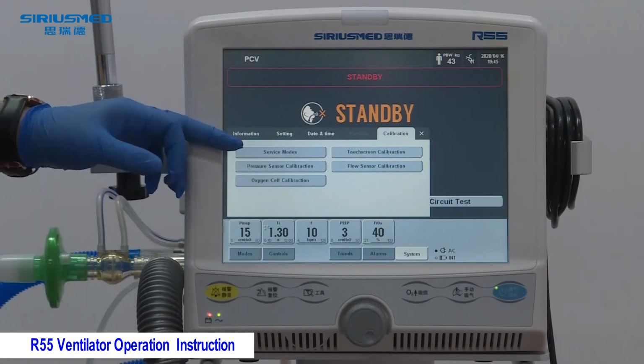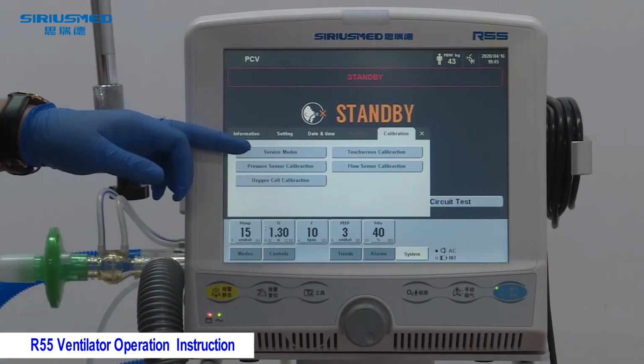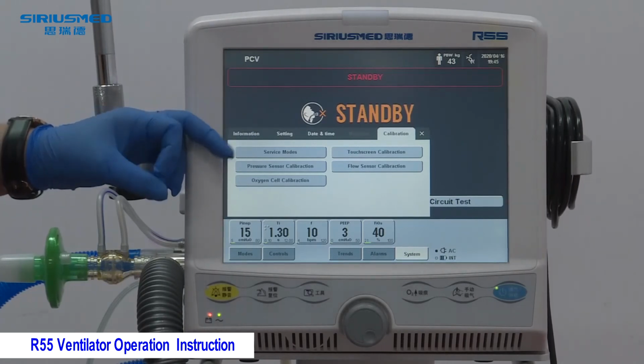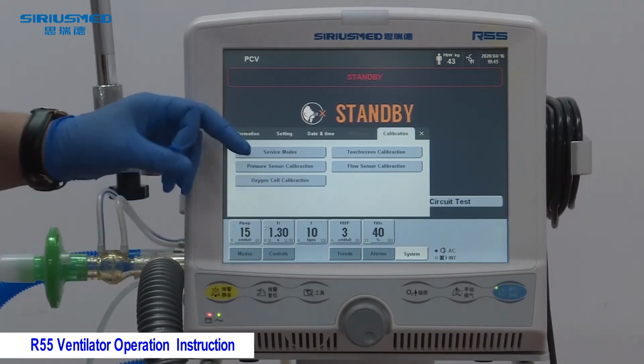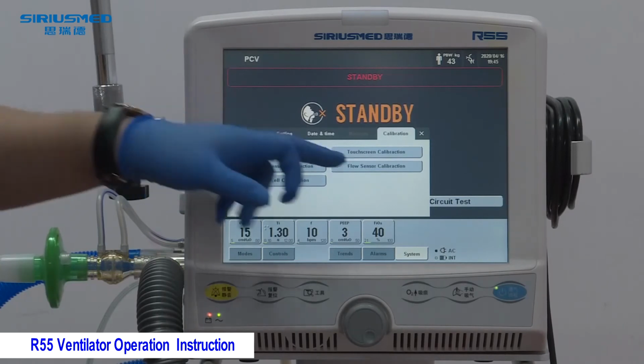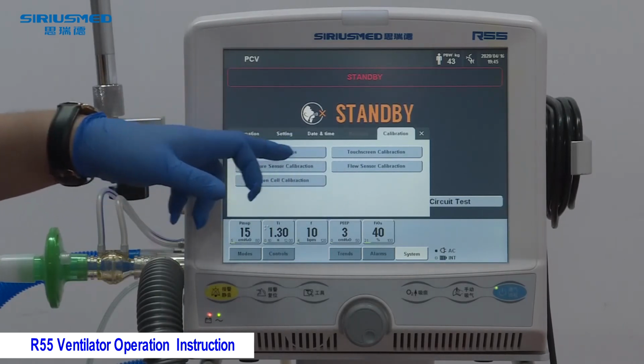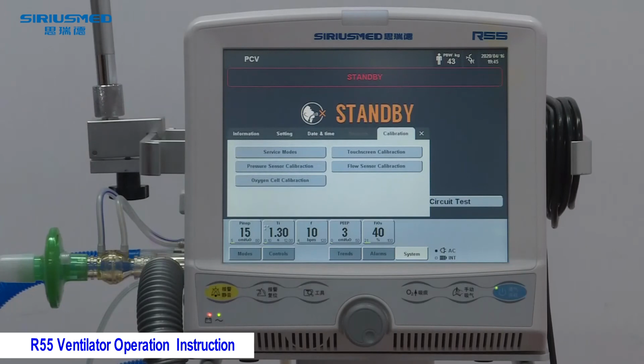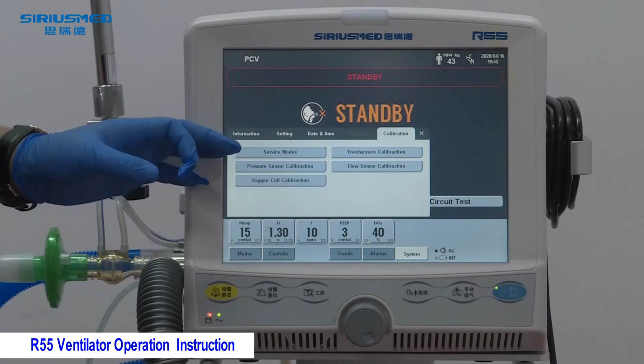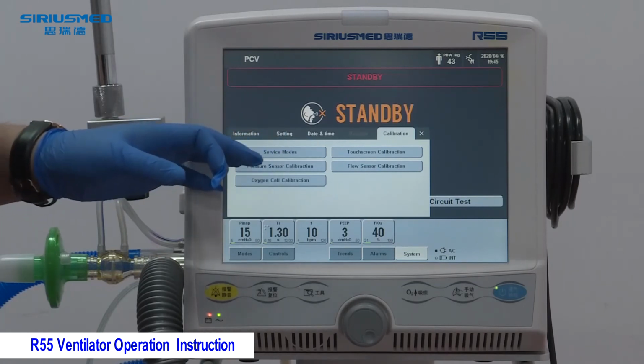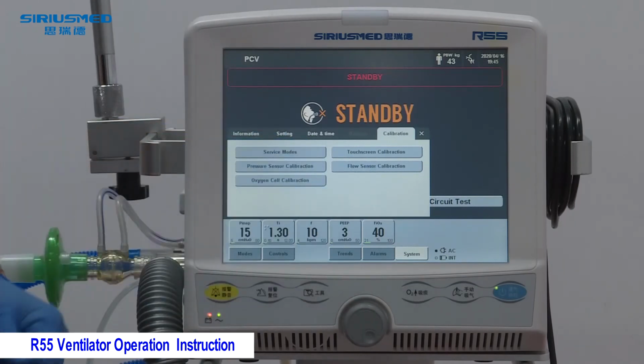And the first one is the service mode. This one is for the engineer. And then the pressure sensor calibration and the flow sensor calibration. These two calibrations are used when the zero of the pressure and flow waveforms is abnormal. If it's abnormal, we need to do the pressure sensor calibration and the flow sensor calibration.